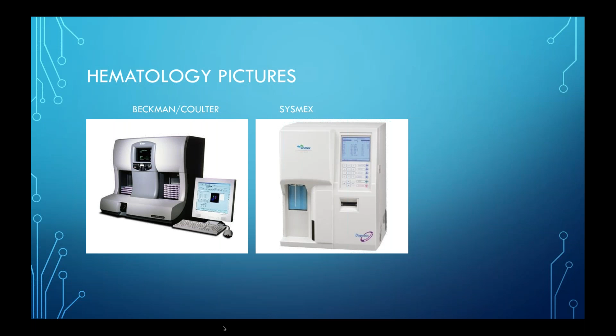What they also do is they'll take blood on every sample that they use and take a drop of blood and smear it onto the slide, and from there they'll do a differential, which is where they actually do a visual count on the blood cells. It used to be in the past where the technicians would have to count 100 blood cells, identify each of the 100 blood cells, and from there that's where the pathologist got to review the differential. We did 100 cells. These units here do 8,196 cells that they count on the differential side. I'll go down a little further.